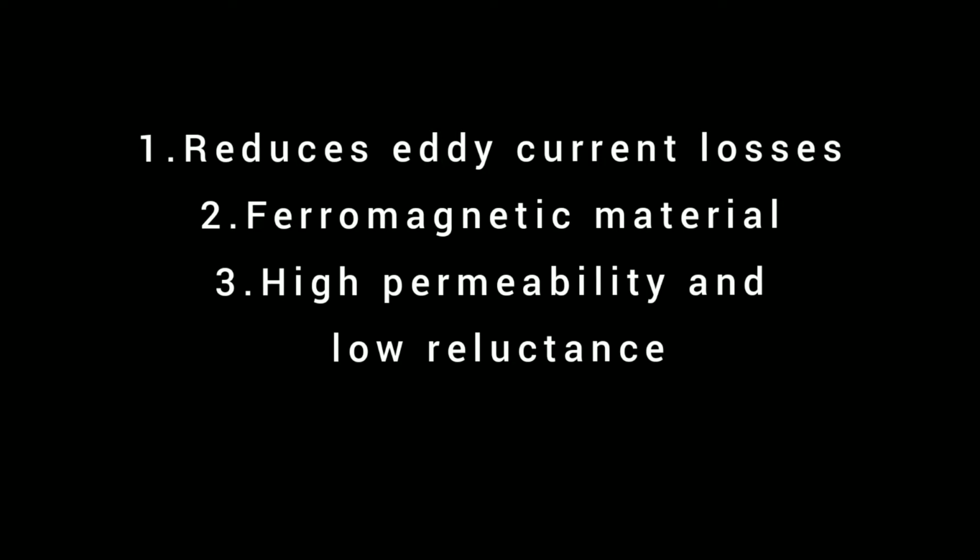Otherwise, it leads to increased excitation current, that is, the reluctance for the flow of flux path increases due to the air gaps. And second, it leads to magnetic hum or noise. Core shape can be stepped form or cruciform form because it reduces the size, weight and cost of the transformer. It has more utilization factor, the amount of winding is reduced, and less insulating material is needed.